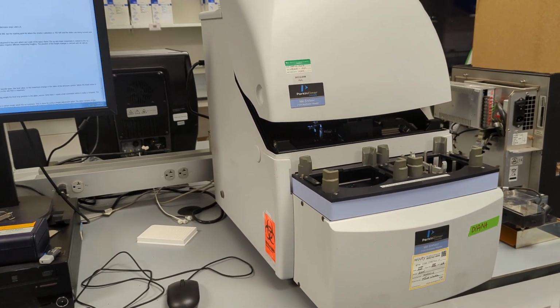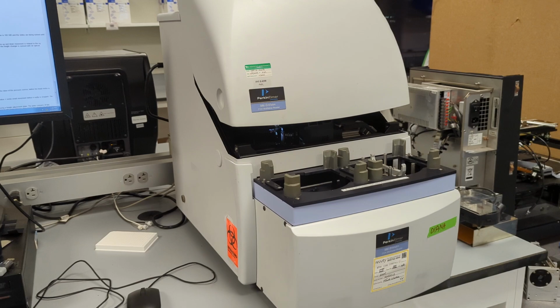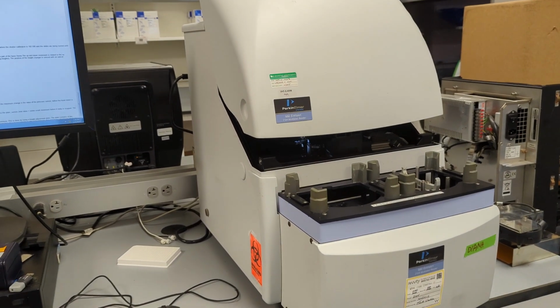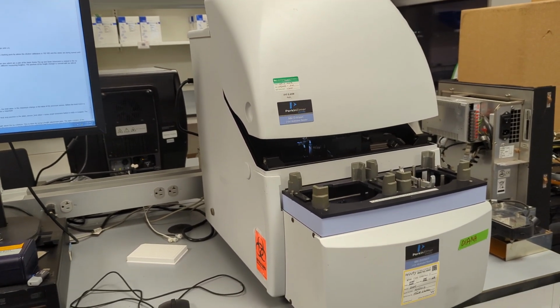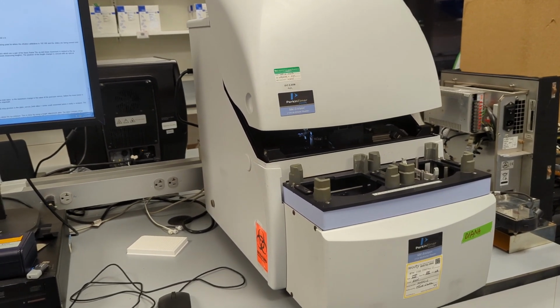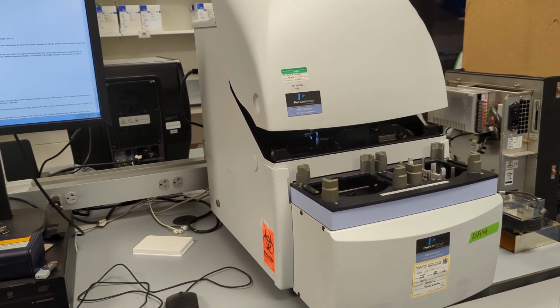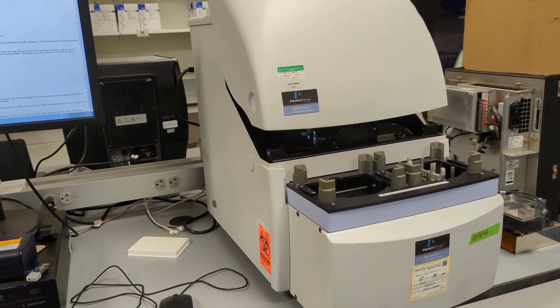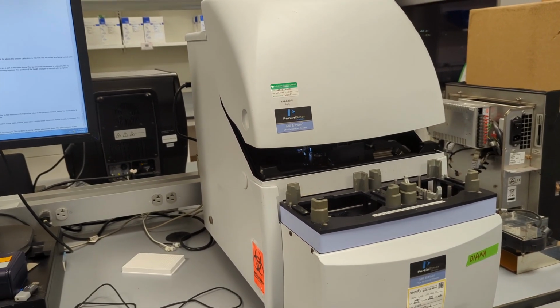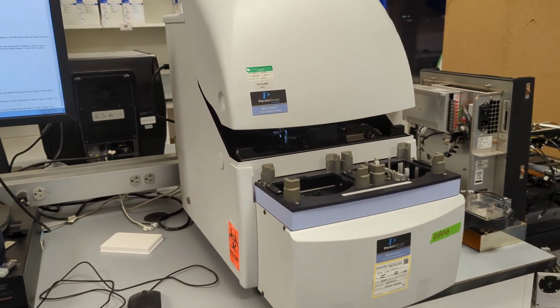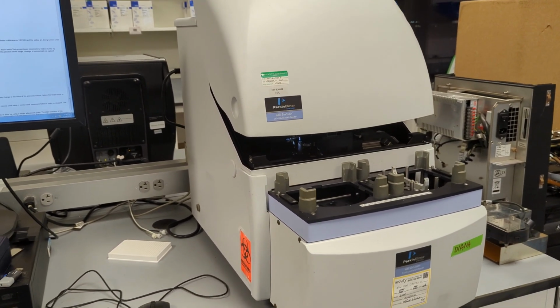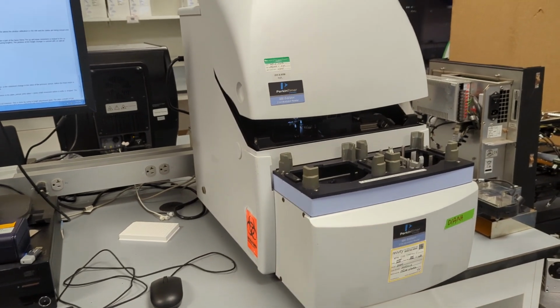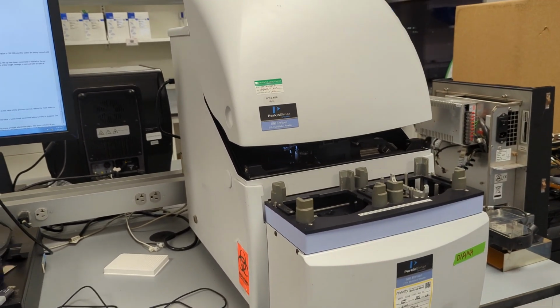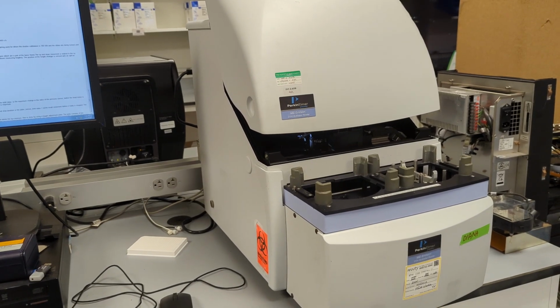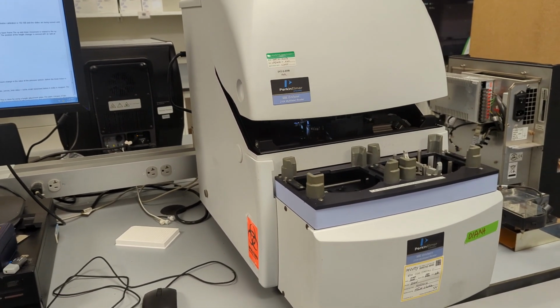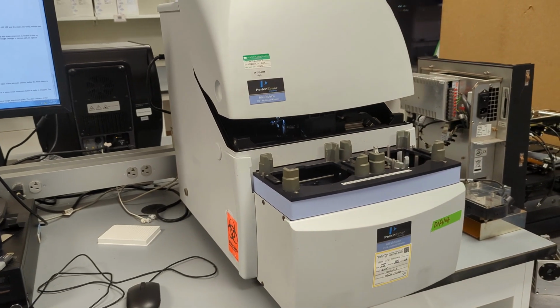And what I mean by that is that with some of the other spectrophotometers we have, or plate readers, for example Molecular Devices, they will sell their customers test plates. So plates for absorbance, fluorescence, luminescence that you can run yourself to qualify or QC your instrument, and you can send them out for certification. That way, if you're in a regulated environment, ISO, GMP, whatever it may be, or GxP, you can do that test in-house, and you can even do some diagnostic tests with that. You can validate repairs with them.